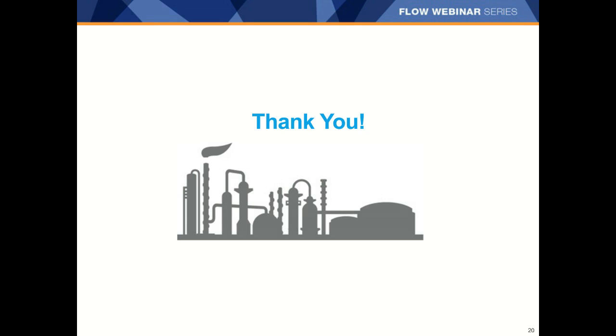First question: for the batching application, is it possible to use one meter for multiple ingredients instead of the setup you showed with one meter? Yes, as long as the meter is properly sized for all of the ingredients, a single meter can be used for multiple ingredients, and it's relatively common to see that done. We would just want to make sure that for any of the ingredients you'd like to charge through a single meter, we run the sizing to make sure the meter's accuracy will hold true with all of those ingredients.